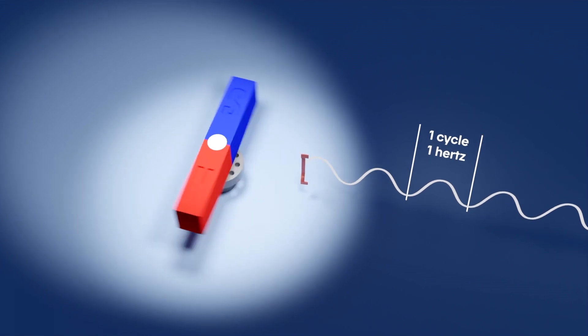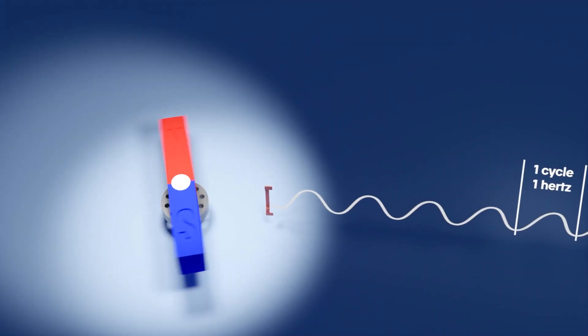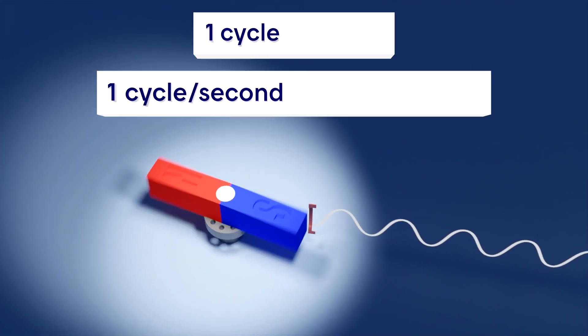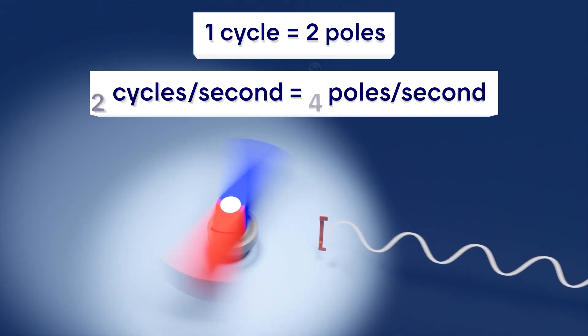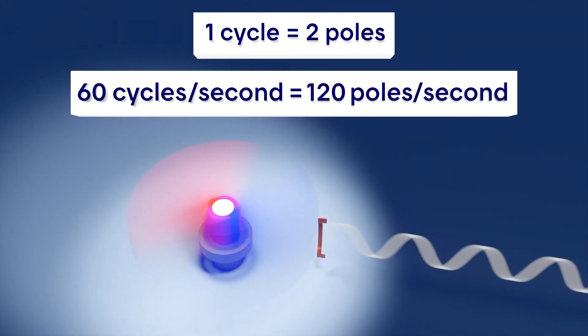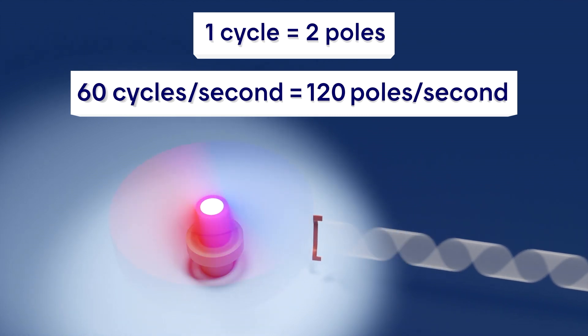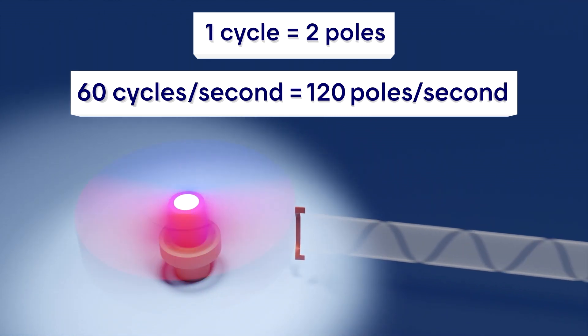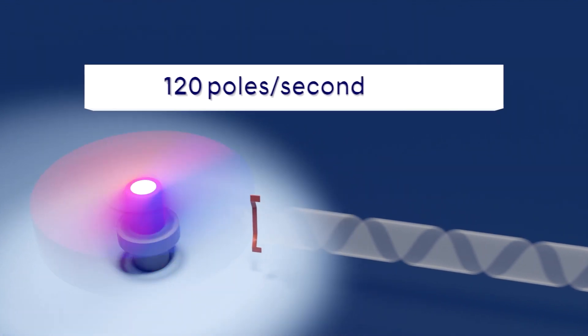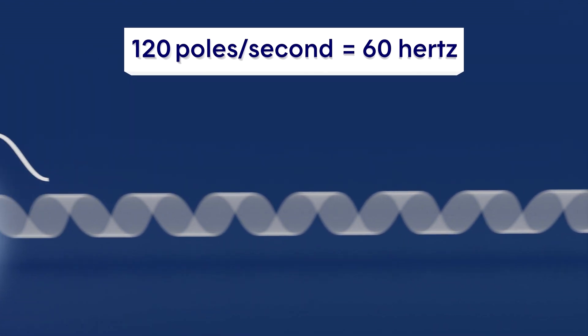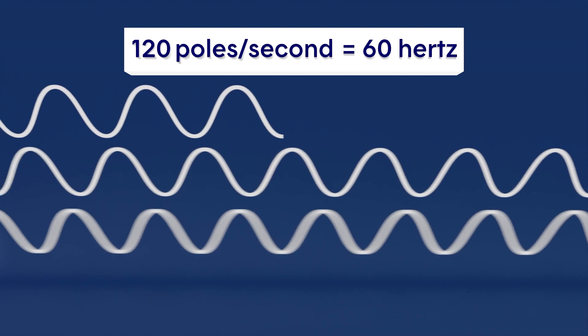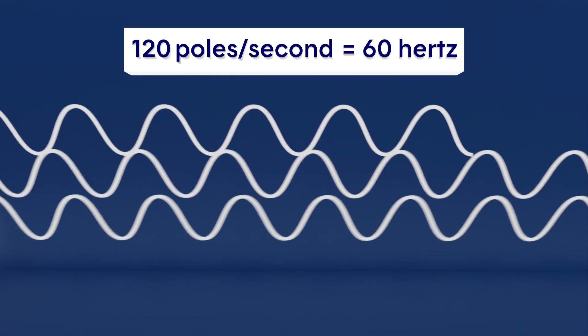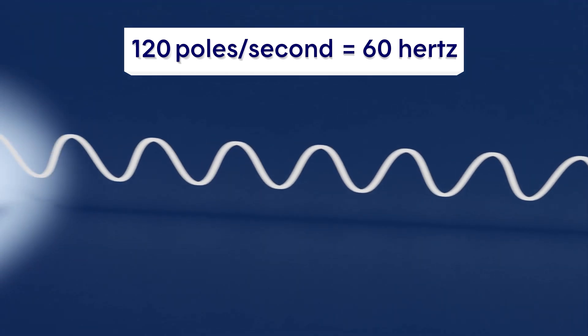The Quebec electric power system runs on 60 hertz. That's 60 cycles per second. A cycle is equivalent to two poles passing in front of the conductor, which means that 60 cycles per second corresponds to 120 poles spinning per second. If we were working with a single magnet, it would have to spin incredibly fast to generate 120 poles per second. And 120 poles per second, that's 60 hertz, the frequency of our power system. If generators had different frequencies, then we wouldn't be able to connect them on a power system. That's why all generators in North America have the same frequency: 60 hertz.